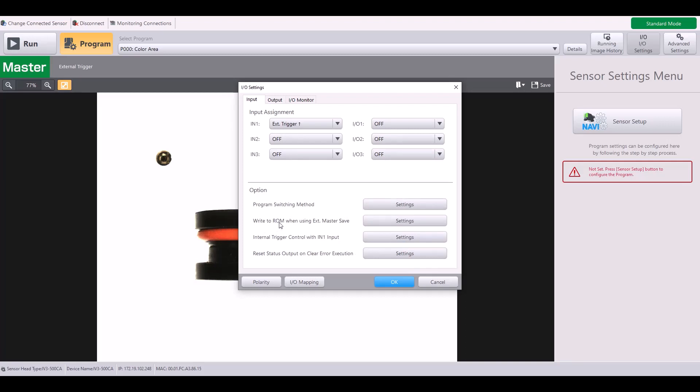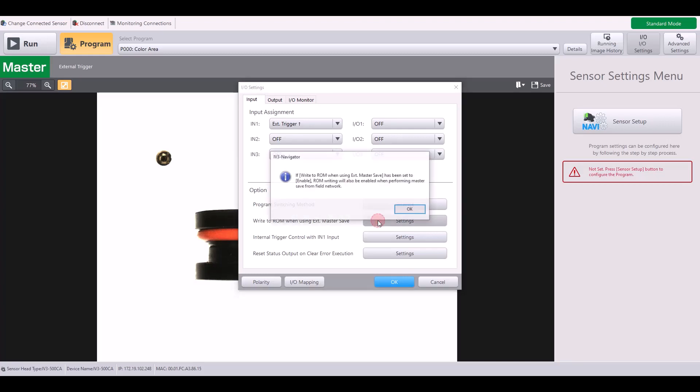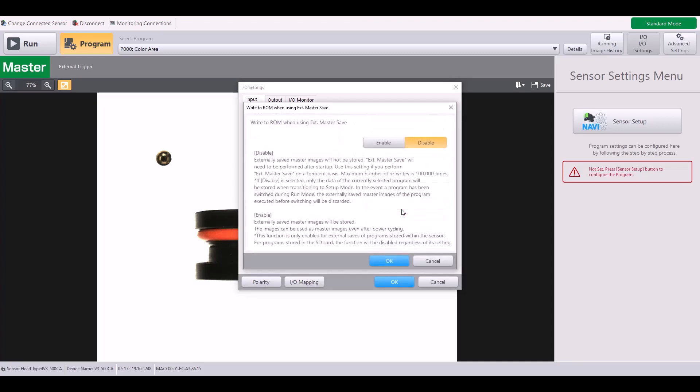There's also this setting for write to ROM when using external master save. So this you can either enable or disable, but if you are using that external master save input and you want to be able to save those images or use them even after a power cycle, you would want to enable this function here.